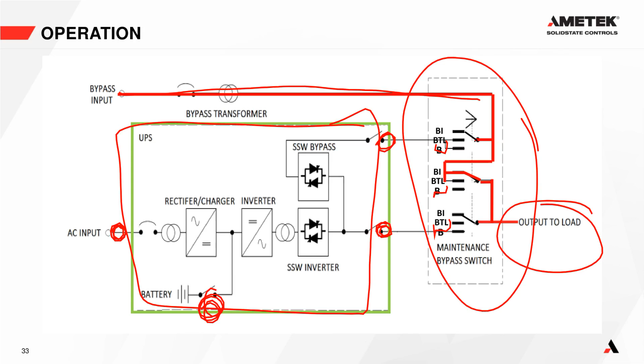You could do this in theory without losing power to any of your load circuits. So that is the true advantage of having an external or remote maintenance bypass switch - it allows you to make the UPS completely volt-free so you can do intrusive maintenance or indeed replace it. That is an RMBS.